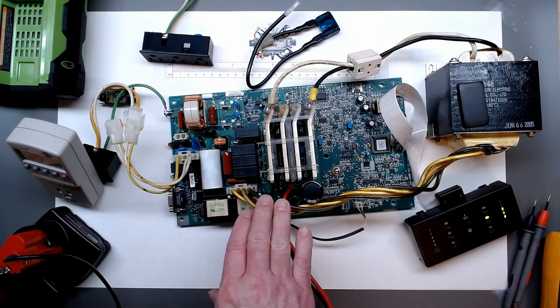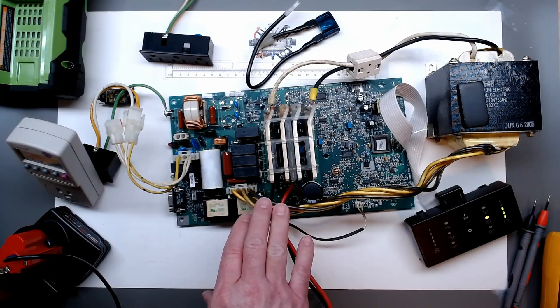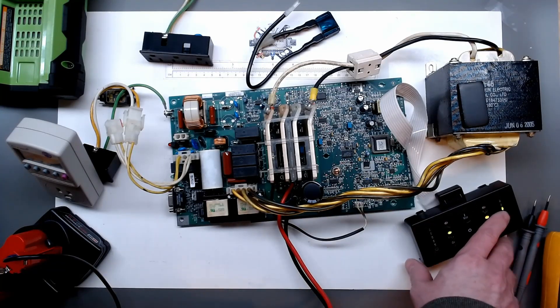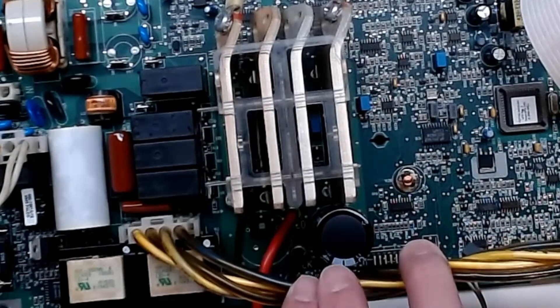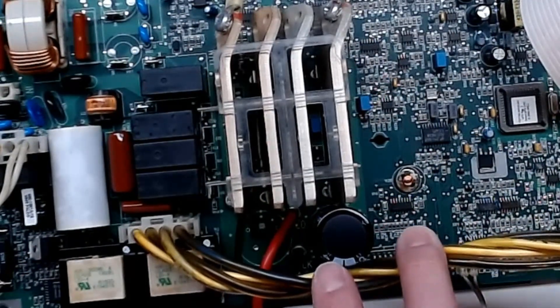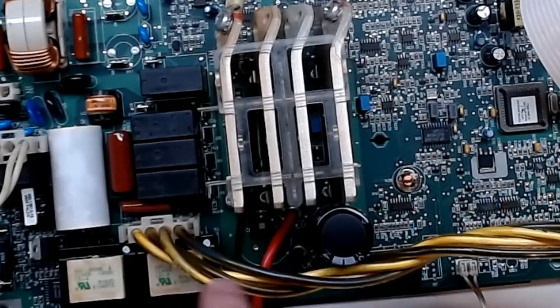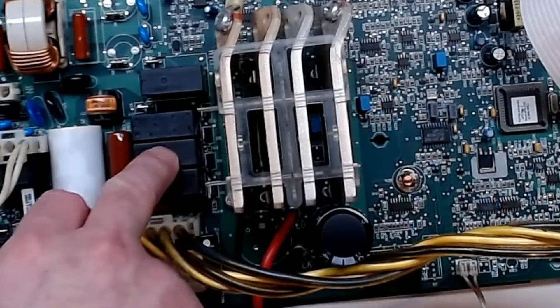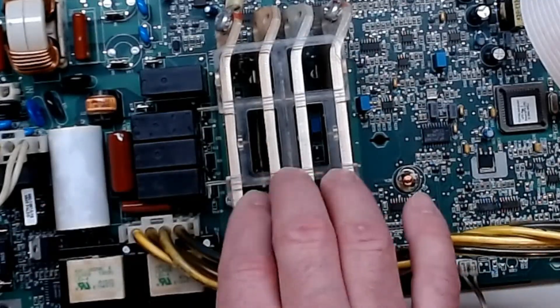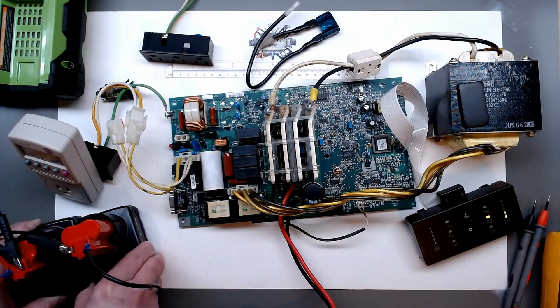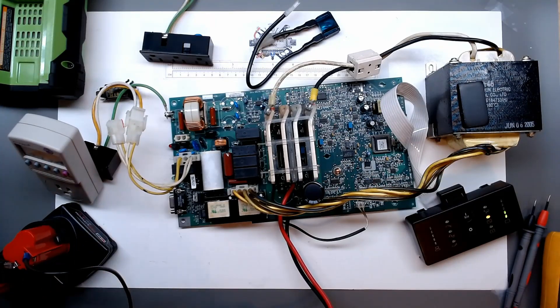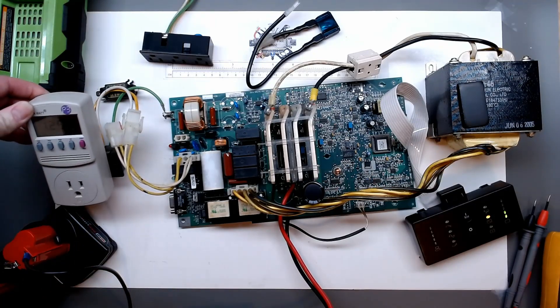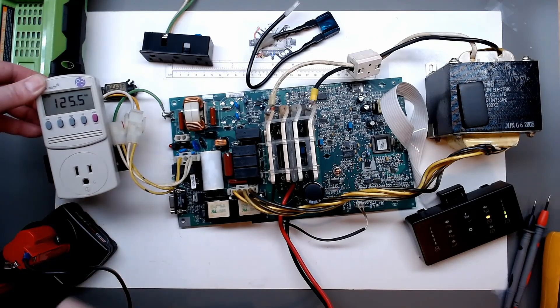One thing we realized, I didn't mark it but I thought this was a 48 volt system and it showed the voltage okay, which was kind of odd. I don't think you can see it on camera, that's a 40 volt cap and I overlooked that. These are 24 volt relays, so I believe this one was actually a 24 volt system. I have two of my M12 Milwaukee batteries in series here just to get my 24 volts for testing only.